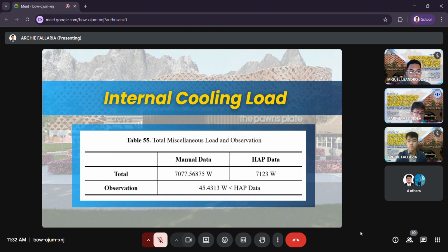So next is the total miscellaneous load and its observation. This table summarizes the miscellaneous equipment load, which accounts for the heat generated by various kitchen appliances and electrical devices essential to restaurant operations. So this includes ovens, refrigerators, freezers, coffee makers, and other cooking and storage equipment, many of which operate continuously or at high intensity. The manual calculation resulted in a total miscellaneous load of 7,077.57 watts, reflecting the substantial internal heat gain from these sources. The HAP software calculated a slightly higher load of 7,123 watts, with a difference of 45.43 watts.